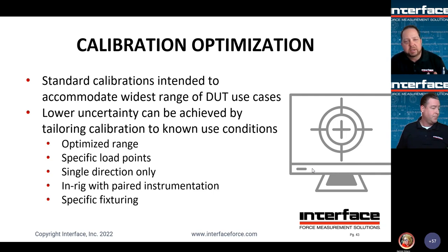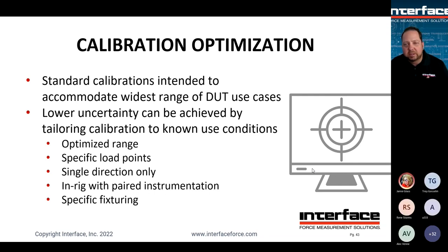Again, if the test condition is a single direction only, then you can basically do a single direction calibration. Hysteresis, for example, only comes into play if you are making a descending load condition, right? So there's things such as that. You can also do an in-rig calibration that Elliot mentioned earlier.